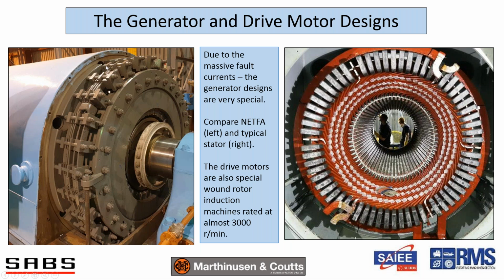This is the NETFA unit, and you can see the stator winding is almost completely encapsulated. You can imagine the short circuit forces: remember, your end winding forces during a short circuit are proportional to the square of the current. So the overhang has basically got to be absolutely rigidly supported, and you can see that in the picture here, with very substantial vibration reducing components. Basically an extremely special design.